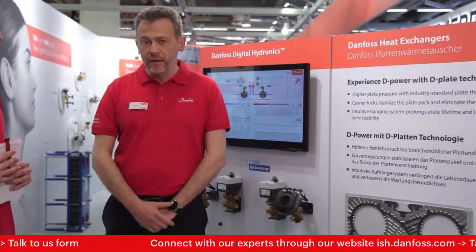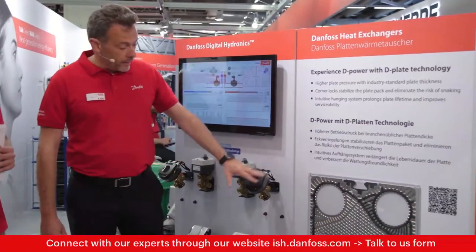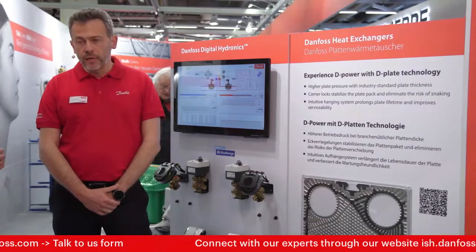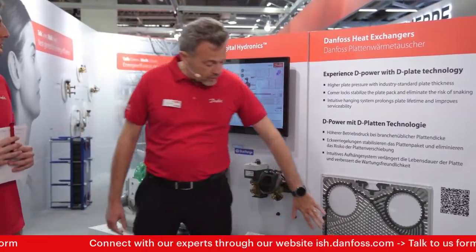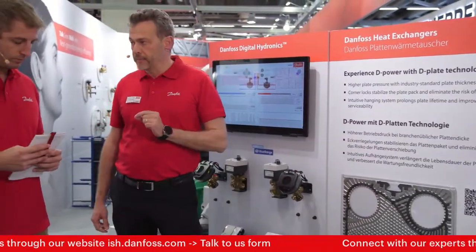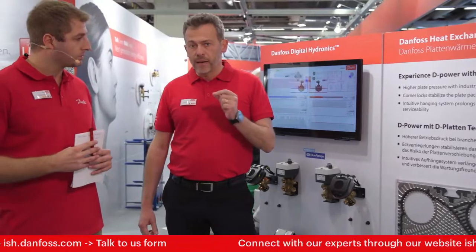Yes. I would like to say that these plates represent very well the DNA of Danfoss to be innovative and exceed expectations. And with these plates, we are able to increase the heat transfer efficiency by up to 10%. We can do that because we have a new design of the heat transfer area, and we are using a thinner plate. Generally, in the market, heat exchangers use 0.5 or 0.4 millimeters. In this case, thanks to the quality of our production, we are able to press 0.3 millimeters.